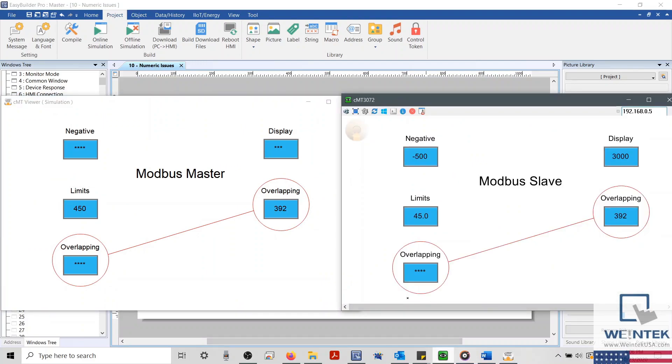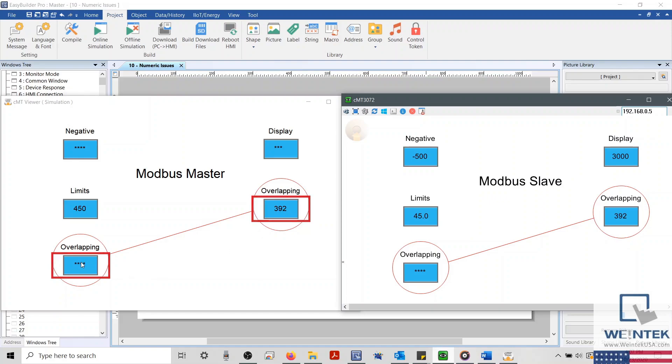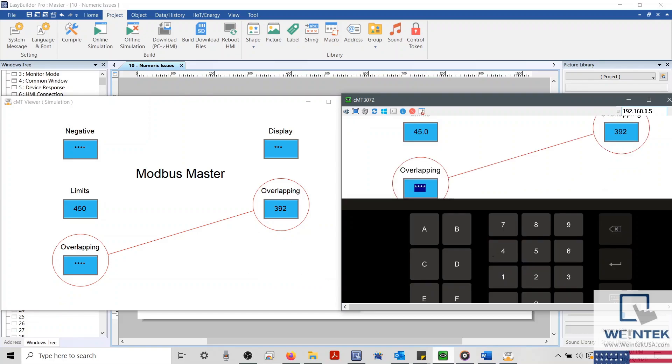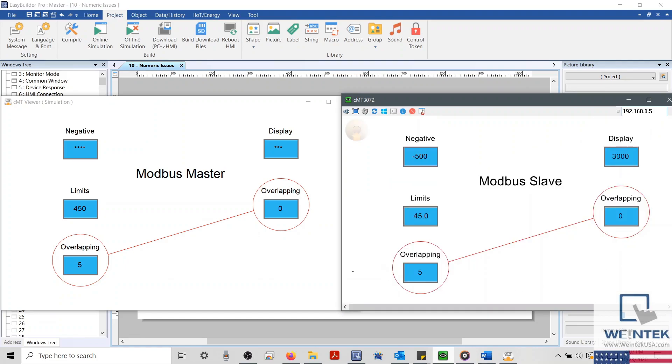Now, the last error is a little complex. We can see that one register appears to display the correct data while the other displays several asterisks. At first glance, we might assume that one of our objects has the correct configuration, and the other object must be incorrect. However, if we test the second Numeric Object, we'll find that this is not the case. To better understand what the issue is, we'll need to reference a tool called the Address Grid.